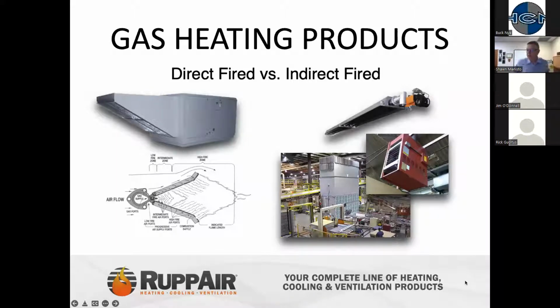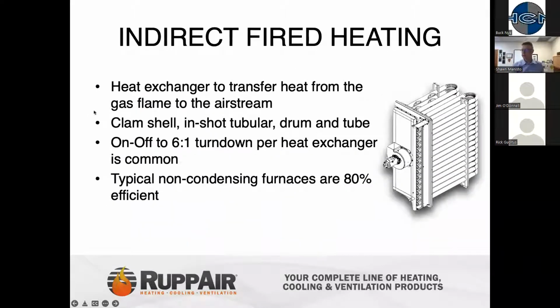So gas-fired heating products can be broken down into two primary categories: direct fired, which you can see on the left-hand side, versus indirect fired systems on the right-hand side. And we're going to talk about all of them. Indirect fired systems have a heat exchanger like we see in this picture right here. In an indirect fired system, we do all the firing outside of the airstream that goes into the building, heat up the exchanger, and transfer that heated air into the space. Commonly, you're going to see that the old style indirect fired units were a clamshell style.